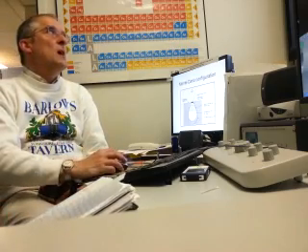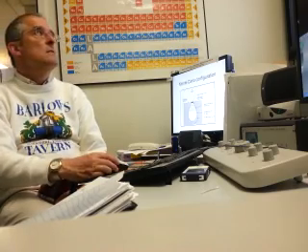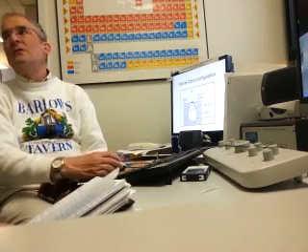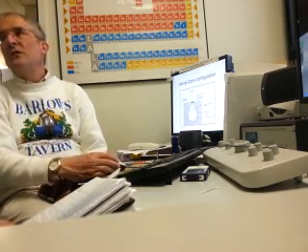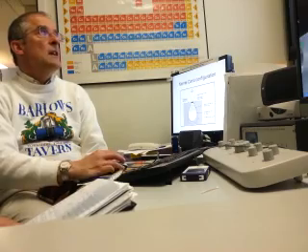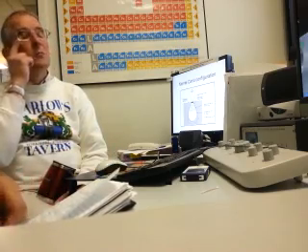So this is the problem with this diagram, people look at it and they think that you can only create secondaries in this little black area, or I guess in the stipple, up and down stipple. But they can take place anywhere in the volume. They just can't be detected by that particular detector. So you can get backscatters that are deep down inside, but they don't exit the sample.